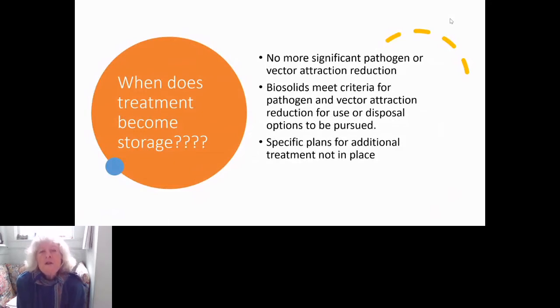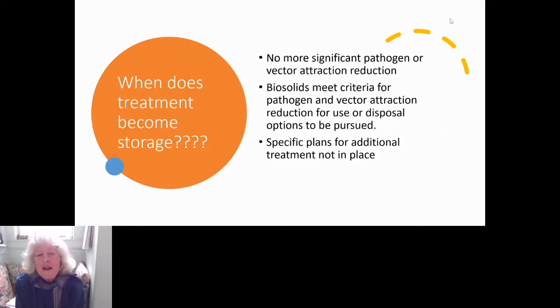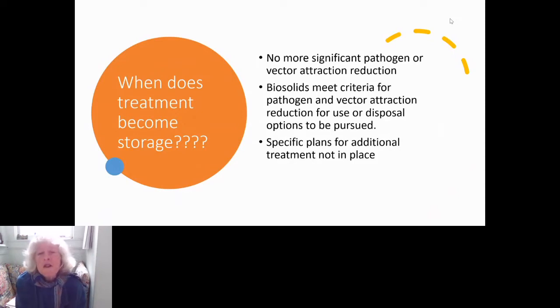There is also the question of when treatment becomes storage. A lot of facilities have drying beds where the sludge dries out and then it sits there. At what point is it no longer treatment and becomes storage? If it's being dried out for the purpose of killing off pathogens or achieving vector attraction reduction in a drying bed, we'd consider it treatment. But if it's been sitting there for several years and is no longer really getting dried out further, then at some point we'd say this is no longer treatment — it's a case-by-case call.